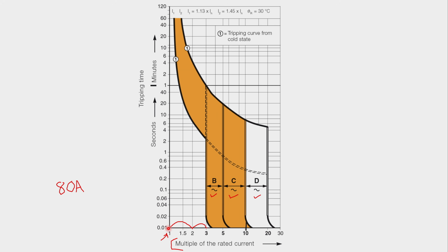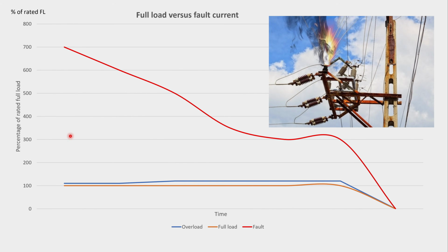But if the current was double, maybe 160 amps, notice that the circuit breaker will now trip much quicker. And if that current was 3 times the rated current, so now we're going to 240 amps, notice that the circuit breaker will trip in less than 0.02 seconds. So we can see that this is dependent on time. And the reason why it's dependent on time is because under a fault condition, the current rises extremely rapidly, and therefore the protection circuit must trip or disconnect that fault as fast as possible, whereas an overload tends to rise slower, or the overload is not anywhere near a fault.